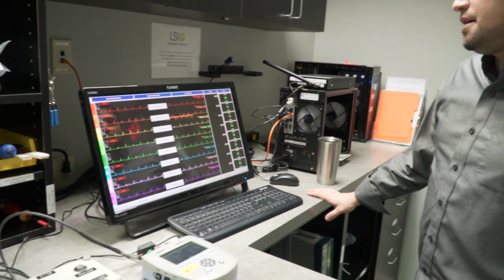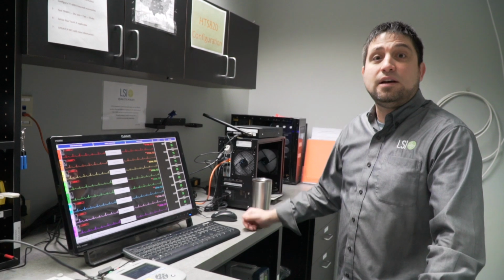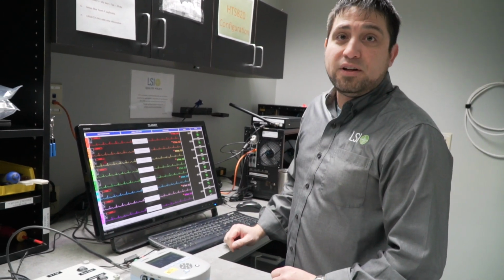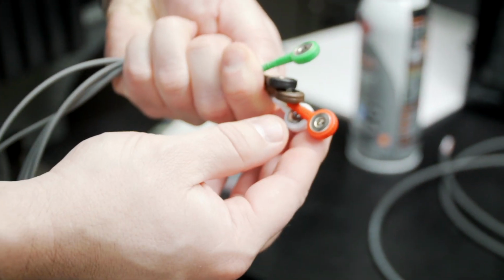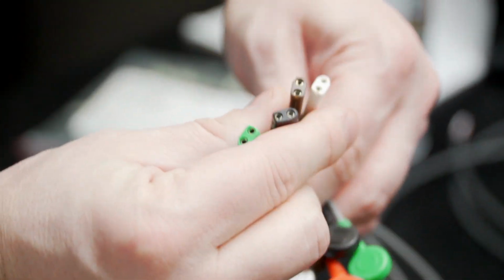Great. So we're able to verify all of our channels, and that in fact we are getting the proper outputs, and that the MCL and leads are going to function as we expect. Cabling is a specialized connector that hooks up to patient electrodes. You can see that they're color coded, and they have that special clip connector. The other end of the connector is a 2-lead which plugs into the transmitter.